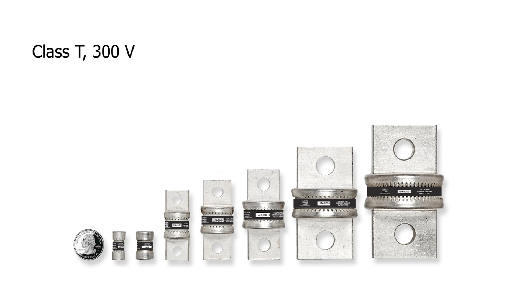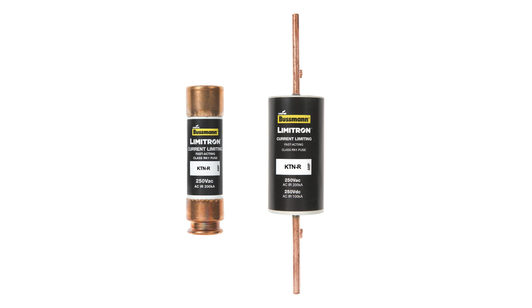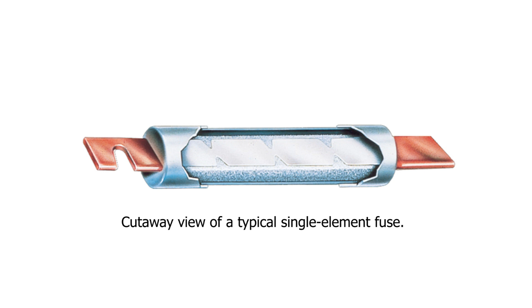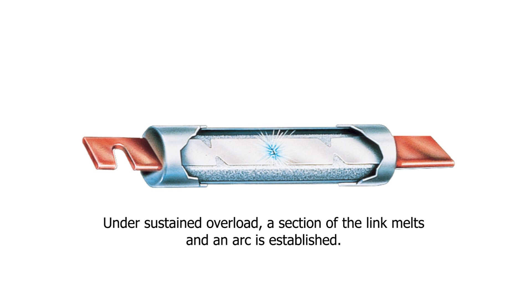Depending upon the amp rating, the fuse may have one or more fuse elements. These elements are electrically connected to the terminals and enclosed in the tube that contains an arc-quenching filler material surrounding the element. Many Bussmann series Limitron fuses are single-element fuses. Under normal operation, when the fuse is applied at or near its amp rating, it simply functions as a conductor. If an overload occurs and persists for more than a short time interval, the element temperature eventually reaches a level that causes a restricted link segment to melt. As a result, a gap is formed and an electric arc established.